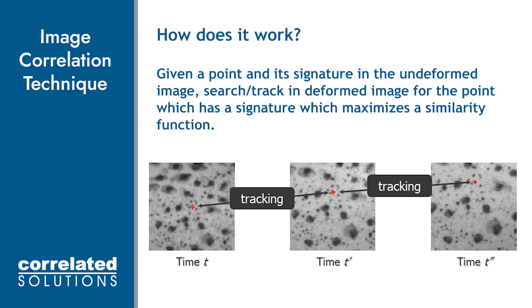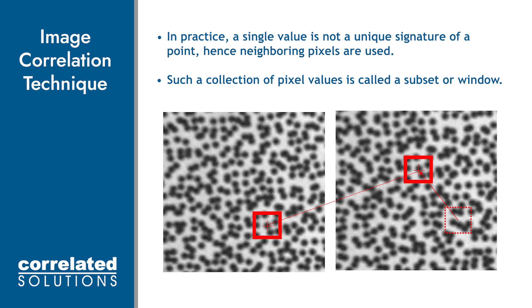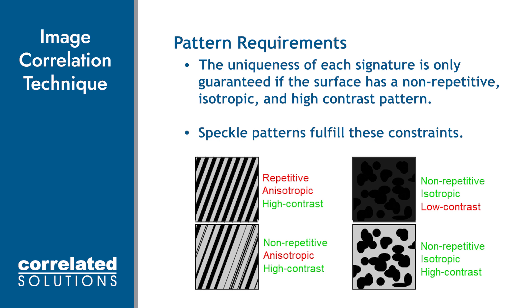Digital image correlation works by tracking points on the test specimen surface that are unique from one another. For this reason, we must apply a speckle pattern to the surface. The speckle pattern provides unique features and markers to track points throughout the surface. The way we track points is by tracking groups of neighboring pixels which we call subsets. The subset size is user defined and should be large enough to provide unique speckle information for all the subsets throughout the surface, while remaining small enough to provide good spatial resolution. In order to provide unique enough information to track every data point or subset, a pattern should be non-repetitive, isotropic, and high contrast.